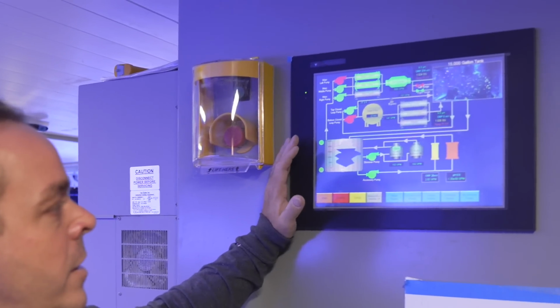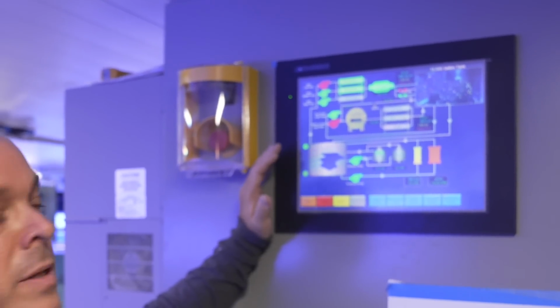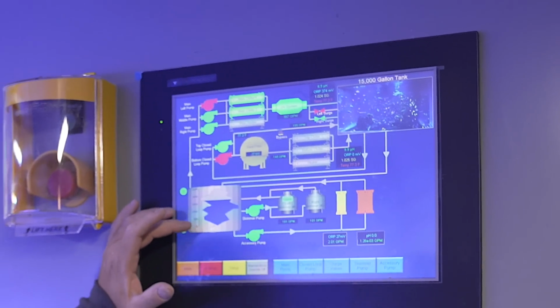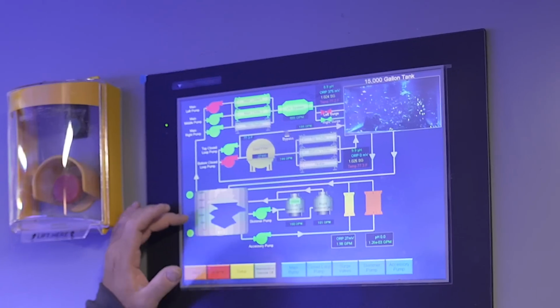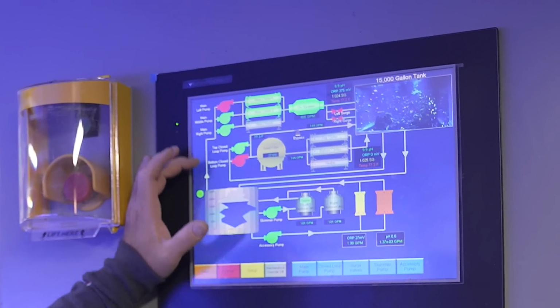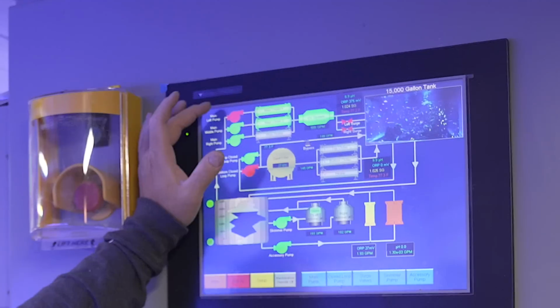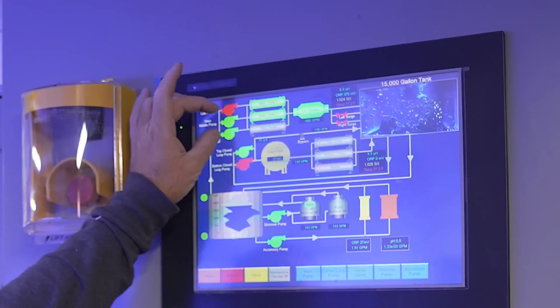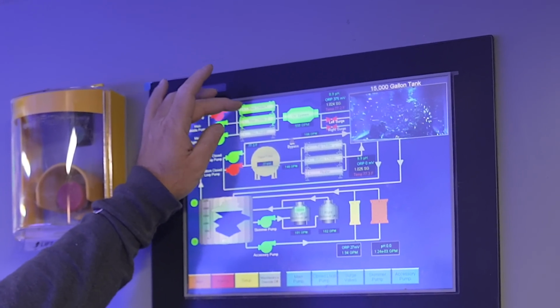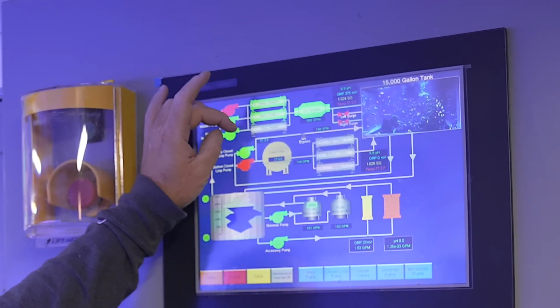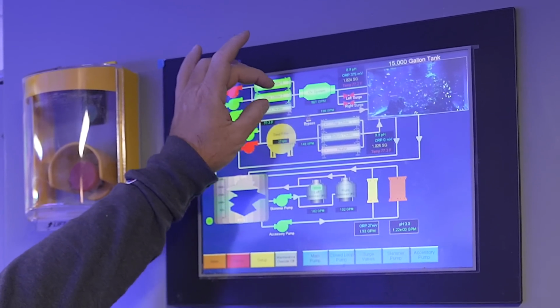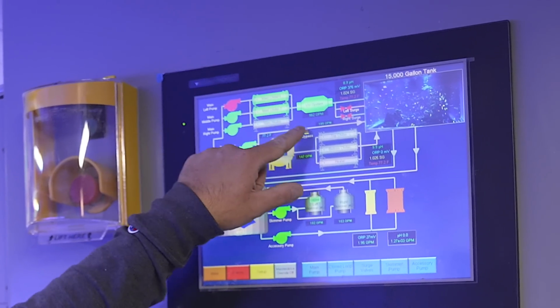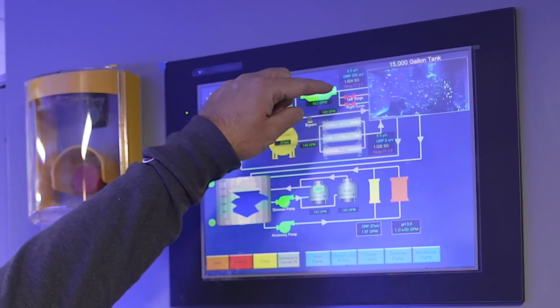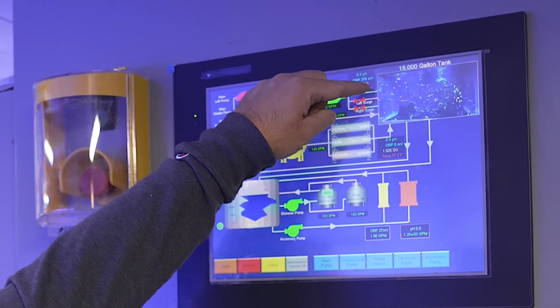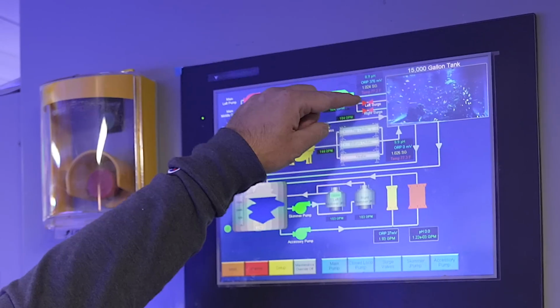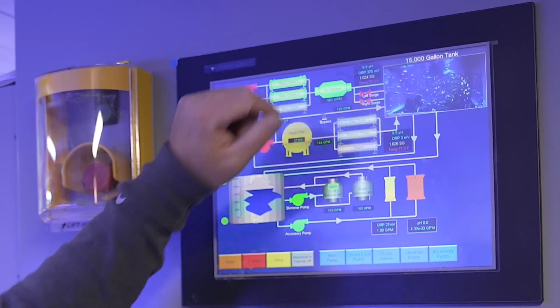On the computer system here, we have a layout of all the piping and the equipment that's running. Here we have the sump level, which is approximately 1,787 gallons of water in the sump right now. The water is sucked out of the sump into the 3 pumps. 2 are running, 1 is not. That is the spare pump. Those then converge and feed 2 chillers that are on currently and a heater that is not. The water comes out of those, mixes back into the mainstream and goes through the UV at 560 gallons a minute. It is then supplied back to the main tank through the main pipe, as well as the two surge valves. The surge valves are red right now because they both happen to be closed at the time of filming this.